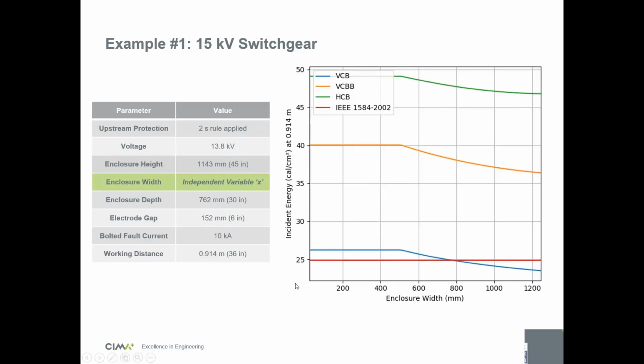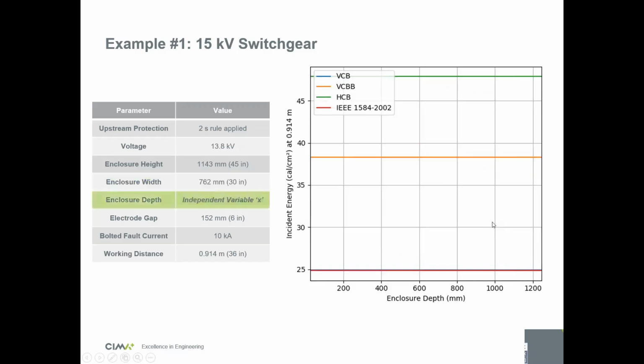It's about the same for the width. The energy is higher when your width is lower, and then the energy goes down if your width goes up a little bit. And the old version stays the same. The depth has absolutely no impact on the energy in this case, because it's not a shallow box. It cannot be shallow. To be shallow, it has to be under 600 volts, height below 20 inch, width below 20 inch, and depth below or equal to 8 inch. In this case it's never the case because you're at 15 kV, so the depth has absolutely no impact.